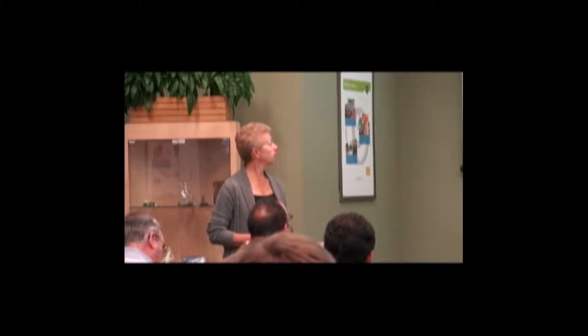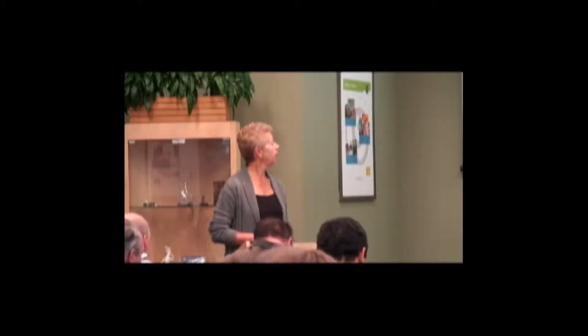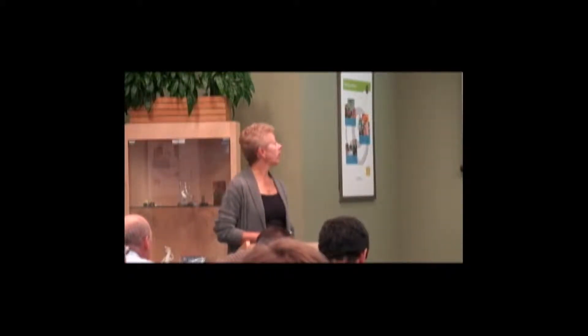Here's a DSC curve. This portion here is the glass transition region. The value 153.28 represents the onset temperature, the midpoint is 162.57, and the recovery is 172.18. The little letter shown here indicates the calculation method used. H stands for half height, I for inflection, E for extrapolated, and W for half width.